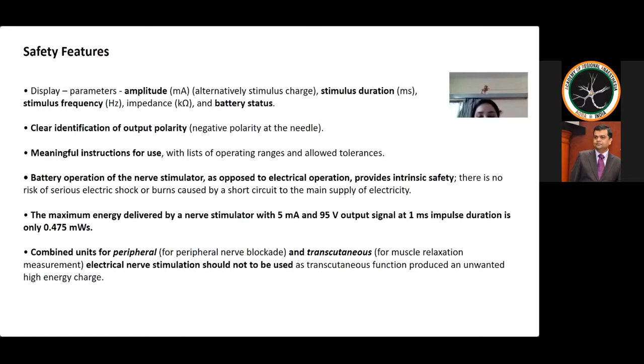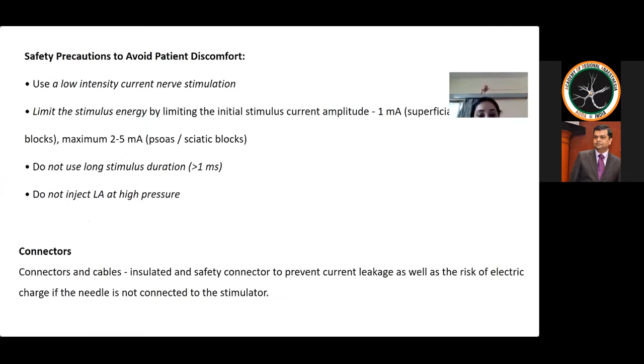Now, the safety precautions: to avoid any patient discomfort, we should use a low intensity current. We should limit the stimulus energy by limiting the initial current amplitude to 1 milliampere for superficial blocks and 2 to 5 maximum for psoas and sciatic blocks. We should not use a stimulus duration of more than 1 millisecond. And the drug, that is the local anesthetic, should not be injected at high pressure, that is more than 15 psi, the opening injection pressure. And the cables and the connectors should be insulated, and safety connectors should be there to prevent the leakage of any current.